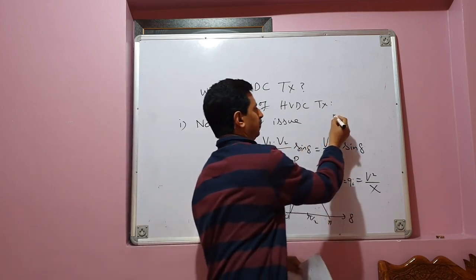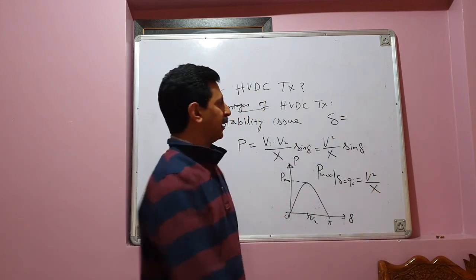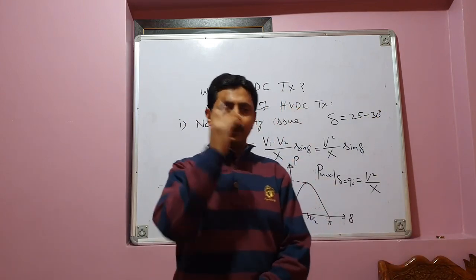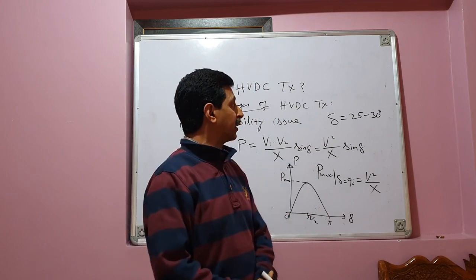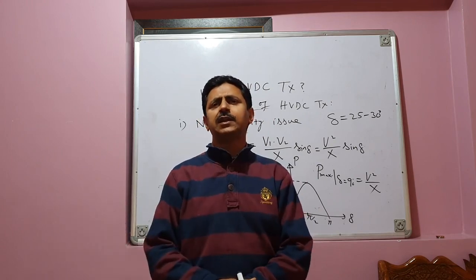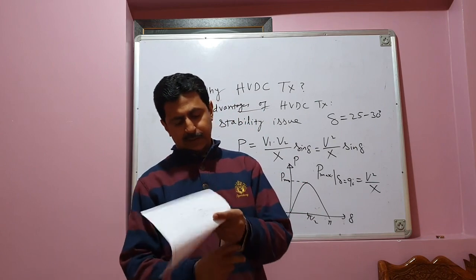So therefore, the permissible operating value of delta is generally 25 to 30 degrees, or 20 to 30 degrees. We operate our transmission system at delta equal to 20 to 30 degrees, or you can say 25 to 30 degrees. This is the optimum value.